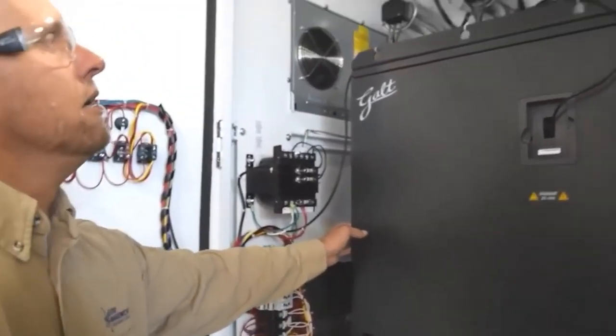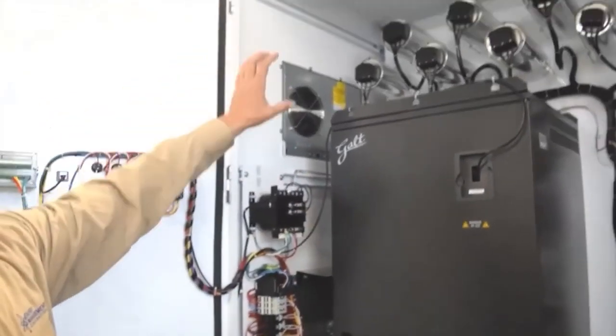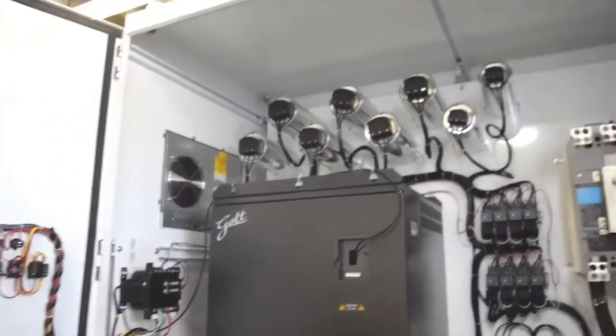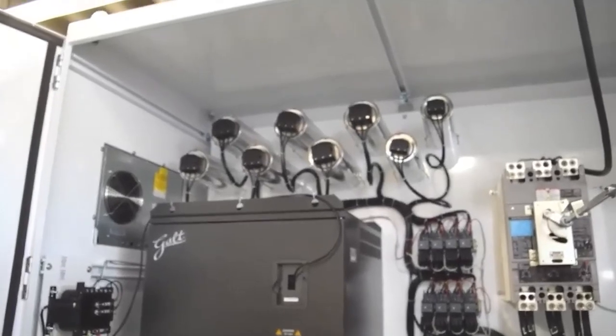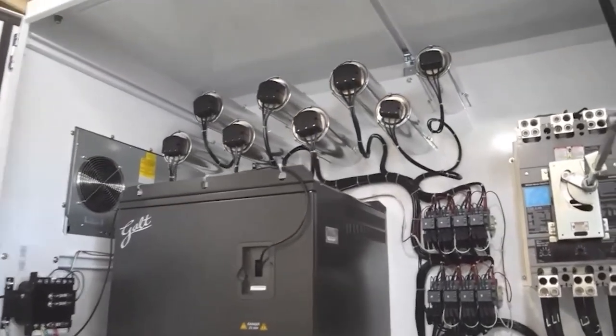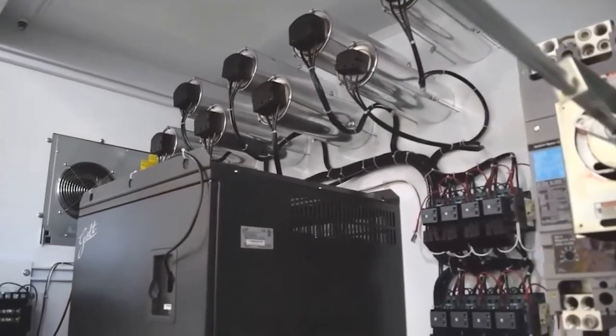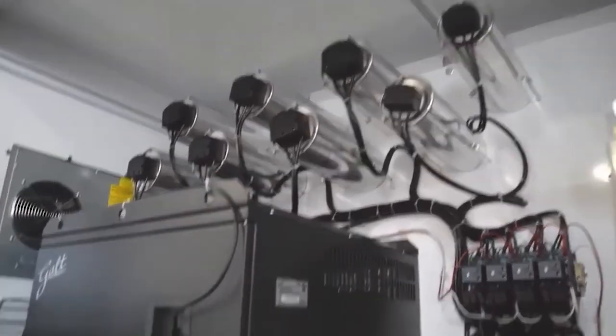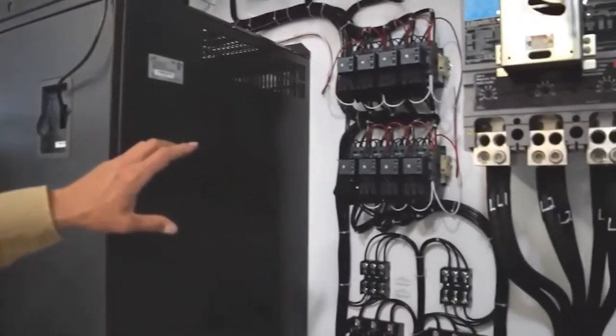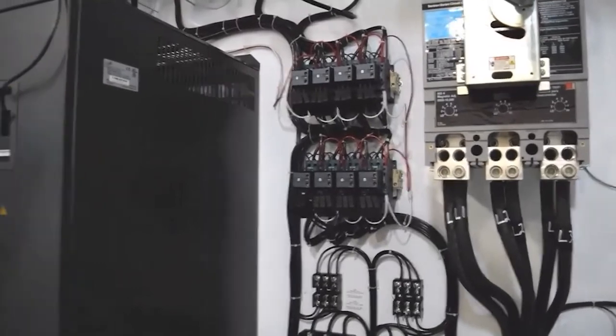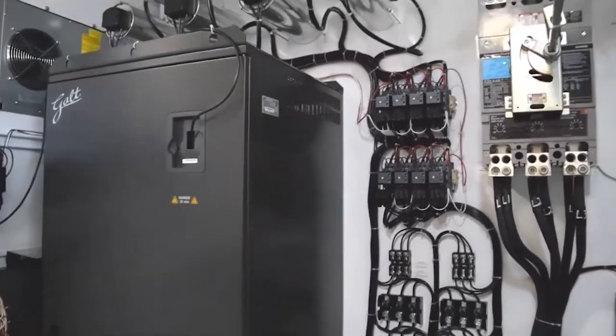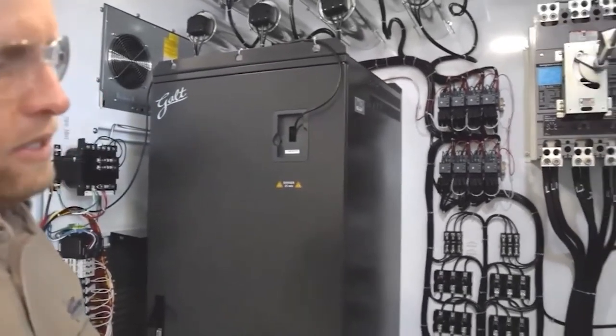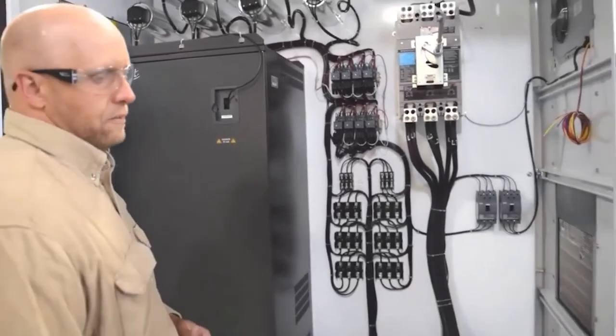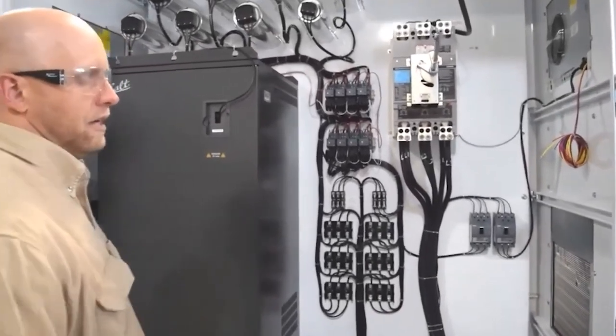Moving across the cabinet, we got our Galt. This is a 700 horsepower VFD. Above the cabinet, we have harmonic filter capacitors. We'll talk a little more in detail about those later. To the side of the VFD, we've got our isolation cutout contactors. And what they are intended to do is turn off the capacitors when the VFD is not in use.